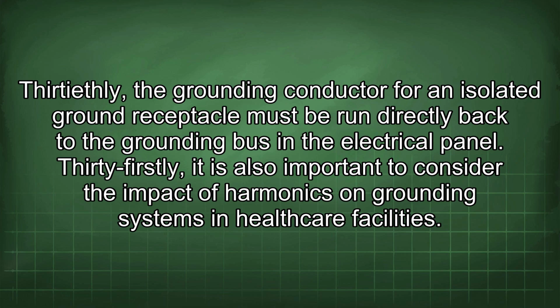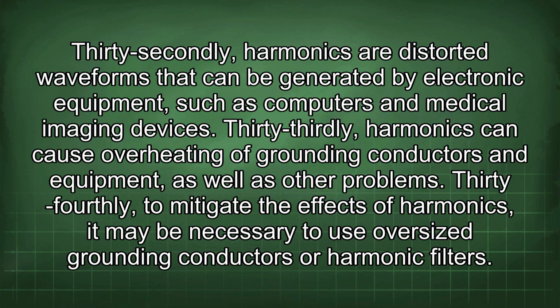electrical panel. 31stly, it is also important to consider the impact of harmonics on grounding systems in healthcare facilities. 32ndly, harmonics are distorted waveforms that can be generated by electronic equipment, such as computers and medical imaging devices. 33rdly, harmonics can cause overheating of grounding conductors and equipment, as well as other problems. 34thly, to mitigate the effects of harmonics, it may be necessary to use oversized grounding conductors or harmonic filters.